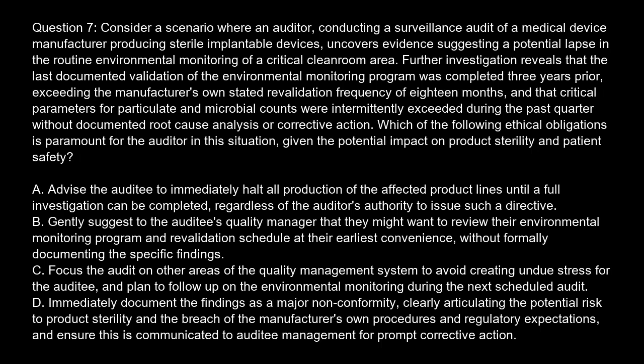Question 7. Consider a scenario where an auditor, conducting a surveillance audit of a medical device manufacturer producing sterile implantable devices, uncovers evidence suggesting a potential lapse in the routine environmental monitoring of a critical cleanroom area. Further investigation reveals that the last documented validation of the environmental monitoring program was completed 3 years prior, exceeding the manufacturer's own stated revalidation frequency of 18 months, and that critical parameters for particulate and microbial counts were intermittently exceeded during the past quarter without documented root cause analysis or corrective action.